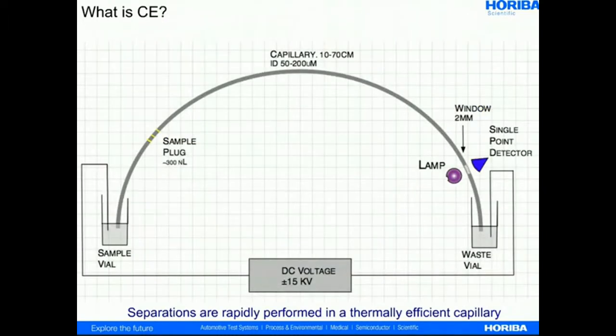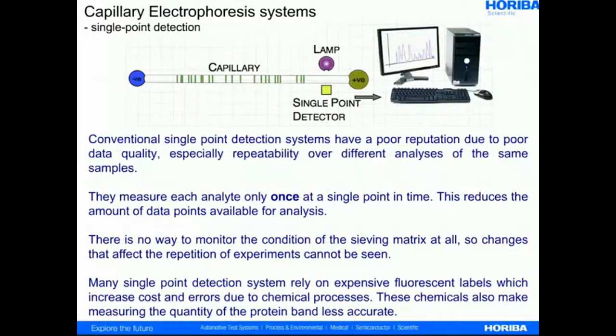What is capillary electrophoresis? It is a technique that has been established for some years, using the thermally efficient capillary to separate molecules over typically 10 to 70 centimeters. The problem with standard capillary electrophoresis is that you only have a single point detector. This means you get just one measurement event of an analyte as it crosses the detector window, which is typically a two millimeter window in the capillary — a single point in time — giving problems particularly with repeatability but also resolution.